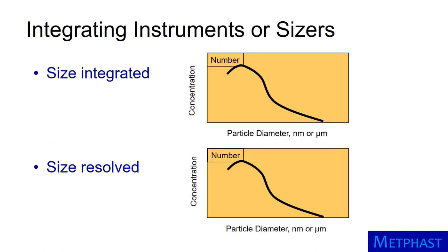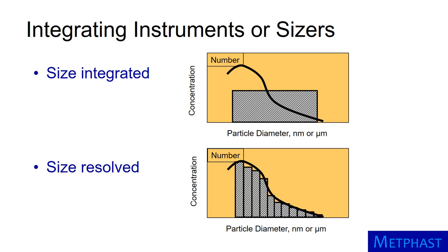There are different types of instruments, with some called size-integrated while others are called size-resolved. A size-integrated instrument provides a single value representing the average particle number concentration across many diameters. In contrast, a sizing instrument provides number concentration in many different size bins. Because these data are size-resolved, they can be used to estimate particle surface area and mass concentration by size.